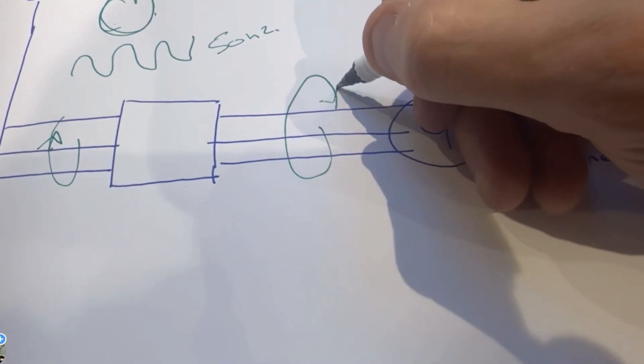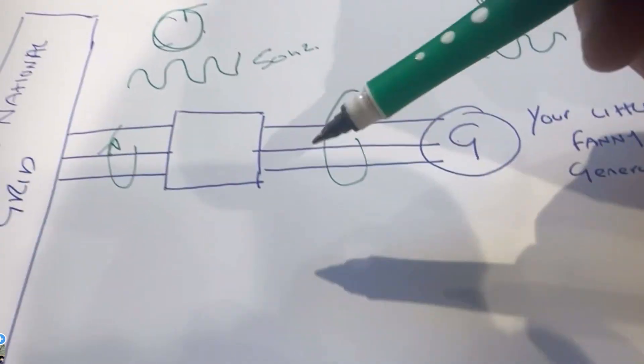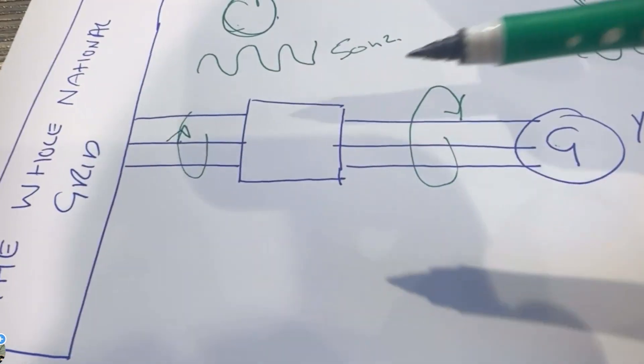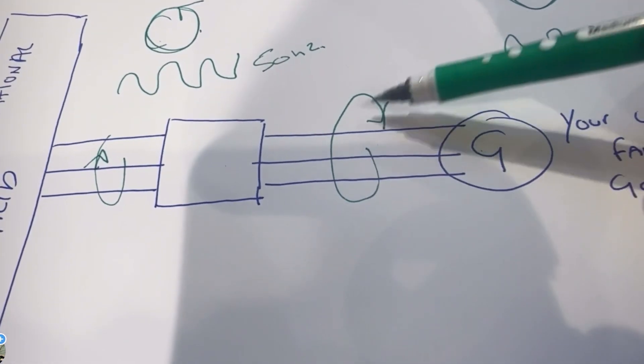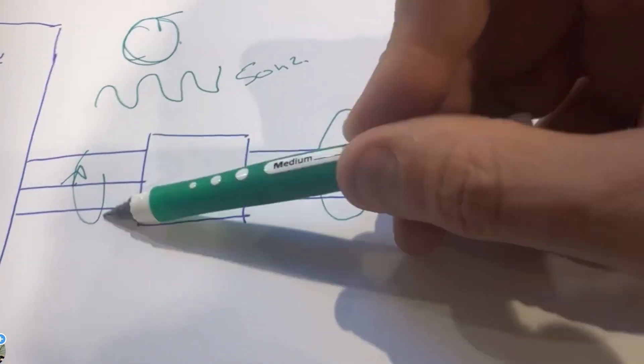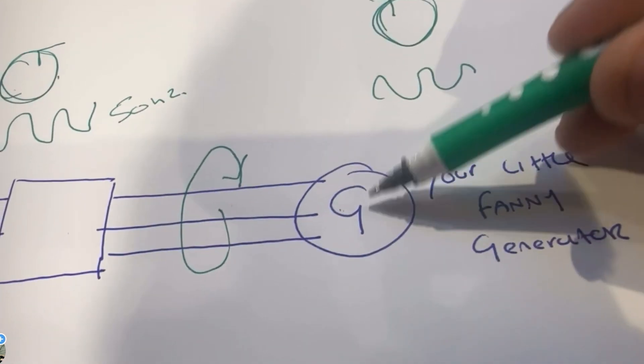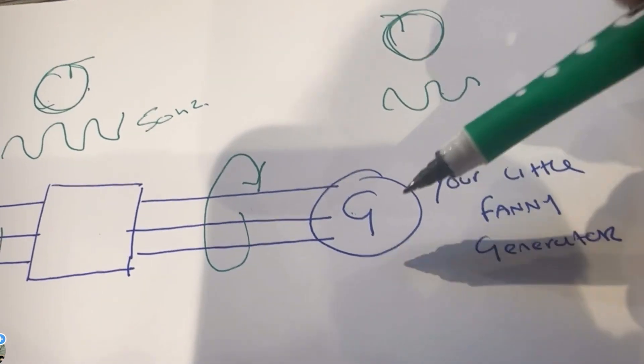When you're installing it you do what they call phasing out, so you make sure that it naturally goes in the same direction. You need to check that though as part of it. You do phasing out which is a thing you do on HV to make sure the phases go in the same direction like this.